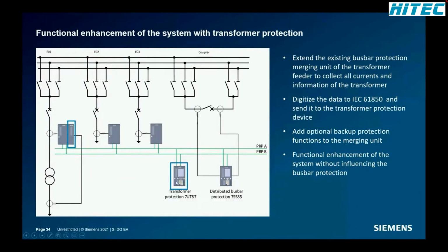This data will be digitized and sent via IEC 61850 communication, which means process bus for the sampled measured values, and GOOSE for the binary information, to the additional transformer protection device 7UT87. All this can be done without affecting the busbar protection functionality. And also, an optional backup protection functionality like overcurrent protection can be added to the merging unit.